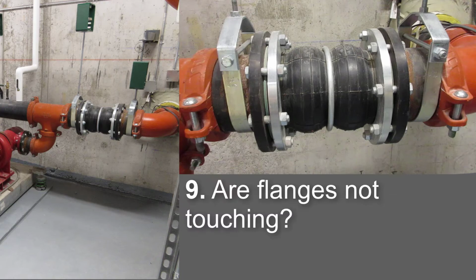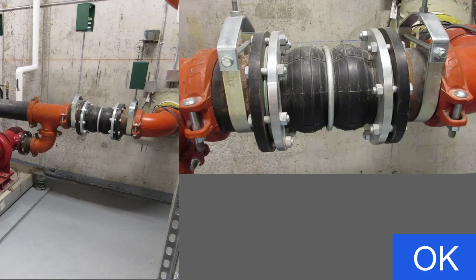And finally, are the flanges not touching each other? Nope, there's definitely an appropriate gap between the flanges where you can see the expansion joint bead and the flange bolts. This is okay. So overall, not a perfect score with the flange bolts installed backwards, but close enough to call it okay.